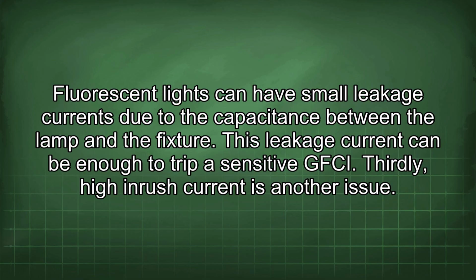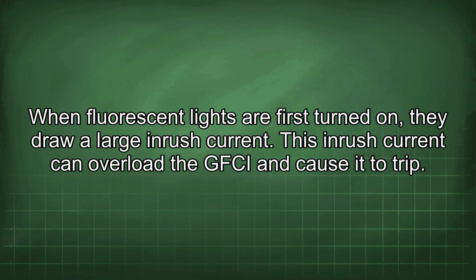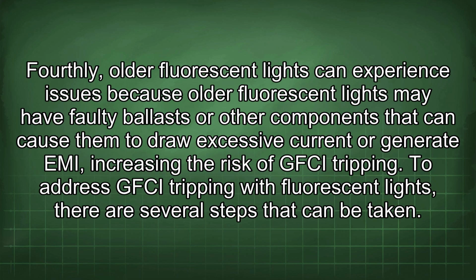Thirdly, high inrush current is another issue. When fluorescent lights are first turned on, they draw a large inrush current. This inrush current can overload the GFCI and cause it to trip. Fourthly, older fluorescent lights may have faulty ballasts or other components that can cause them to draw excessive current or generate EMI, increasing the risk of GFCI tripping.